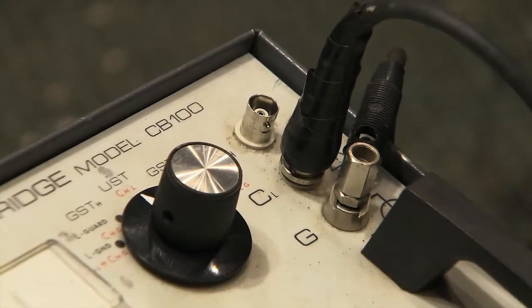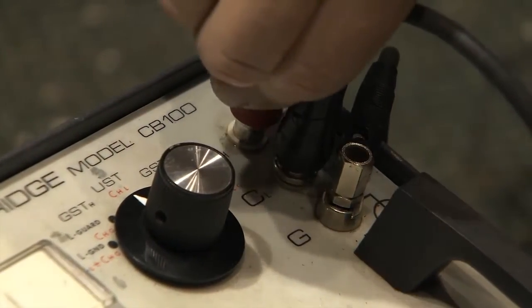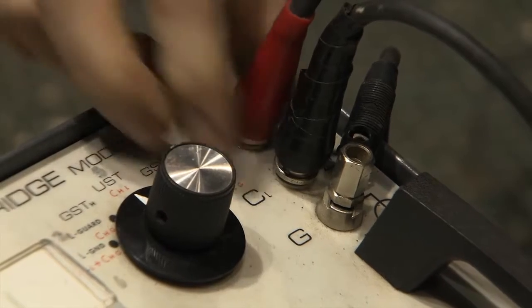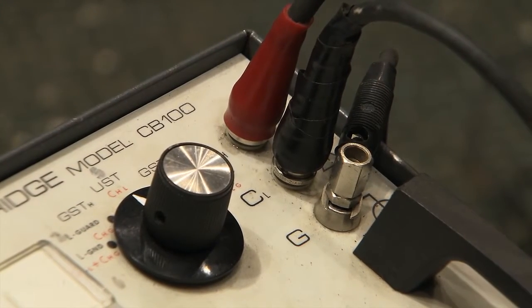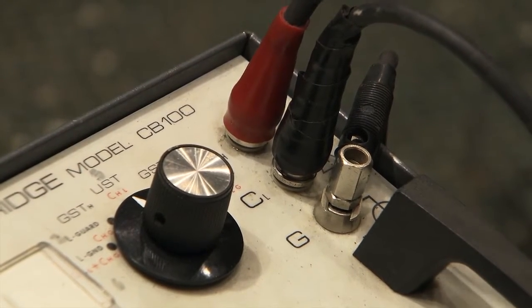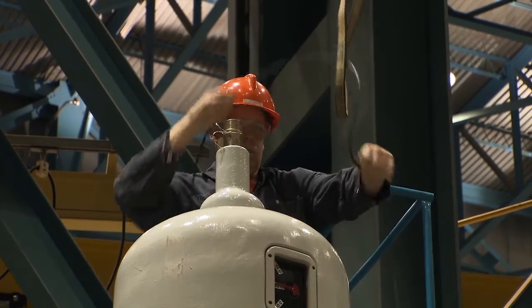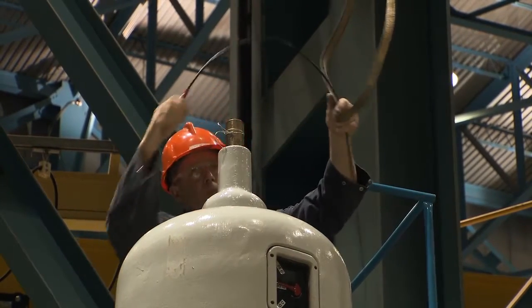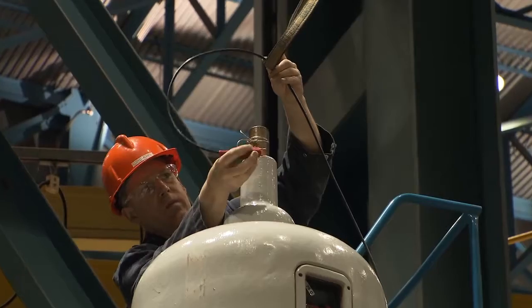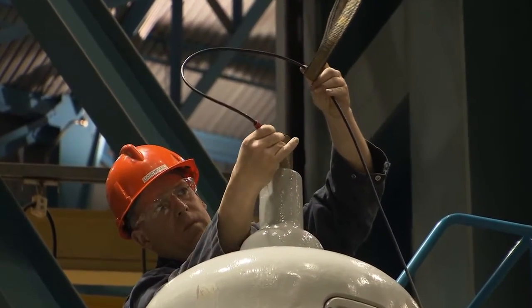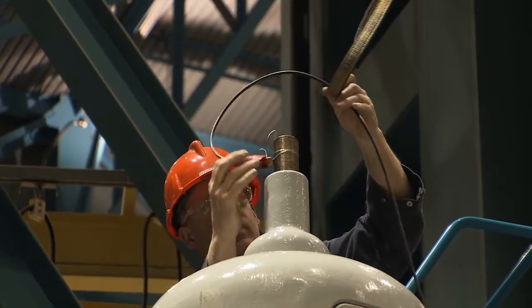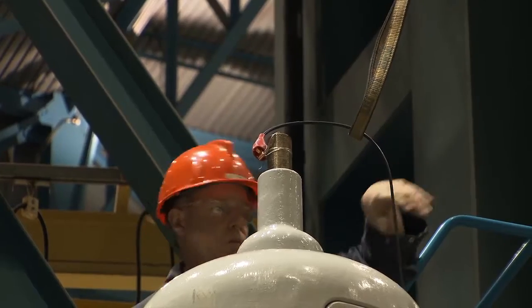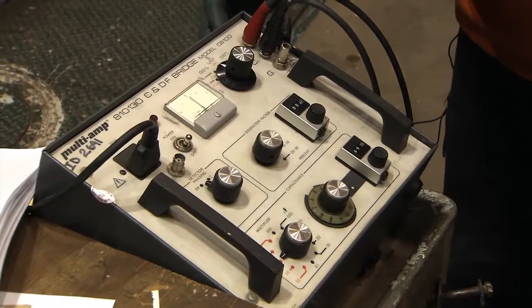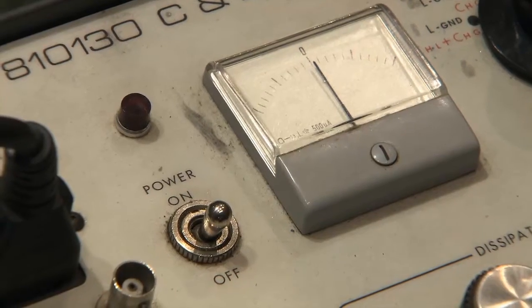Connect one end of the high voltage lead that sends out the electric current, the red lead, to the high voltage terminal labeled C(H) on the capacitance and dissipation factor bridge. Connect the other end of the lead, also red, to the bare copper strand wrapped around the top of the terminal lead. All of the cables are now connected, and the UST test can be conducted.